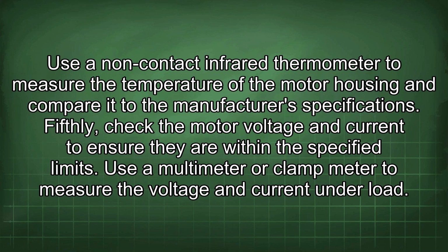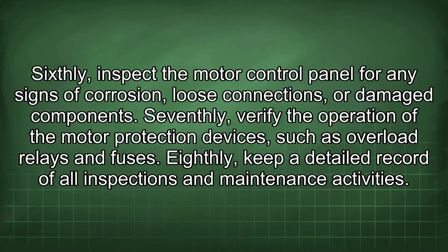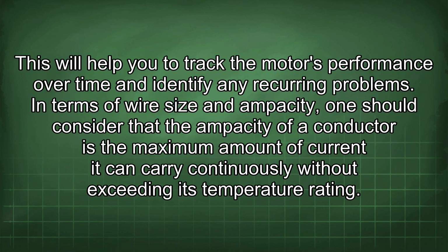Fifthly, check the motor voltage and current to ensure they are within the specified limits. Use a multimeter or clamp meter to measure the voltage and current under load. Sixthly, inspect the motor control panel for any signs of corrosion, loose connections, or damaged components. Seventhly, verify the operation of the motor protection devices such as overload relays and fuses. Eighthly, keep a detailed record of all inspections and maintenance activities. This will help you to track the motor's performance over time and identify any recurring problems.